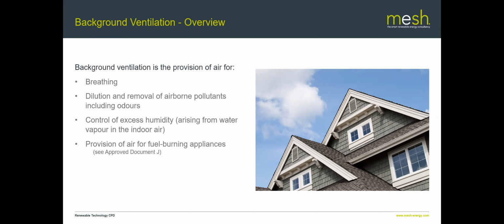Second one is background ventilation. Background ventilation is the provision of air for breathing, dilution and removal of airborne pollutants, including low-level background odors, and control of excess humidity, typically arising from things like bathrooms and utility rooms where you're using hot water and steam is being produced. And it's also for the provision of air for fuel burning appliances. And that's covered off in a separate document from Approved Document F, which we're going to look at, which is the ventilation side. That particularly is covered off in Approved Document J. So quite often you will need to refer to Approved Document F as a starting point, and then also on to Approved Document J for particular rooms where perhaps you've got a wood burning stove that's not room sealed or something like that.